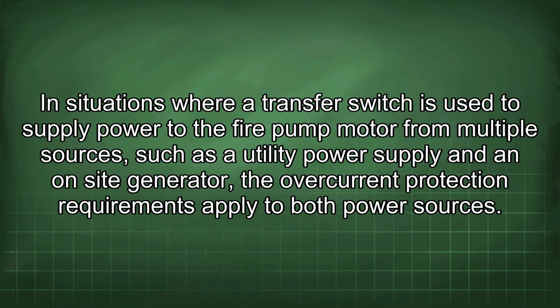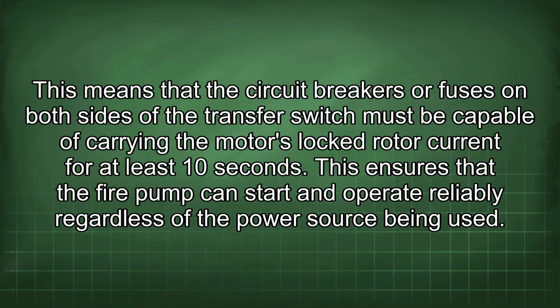In situations where a transfer switch is used to supply power to the fire pump motor from multiple sources, such as a utility power supply and an on-site generator, the overcurrent protection requirements apply to both power sources. This means that the circuit breakers or fuses on both sides of the transfer switch must be capable of carrying the motor's locked rotor current for at least 10 seconds. This ensures that the fire pump can start and operate reliably regardless of the power source being used.